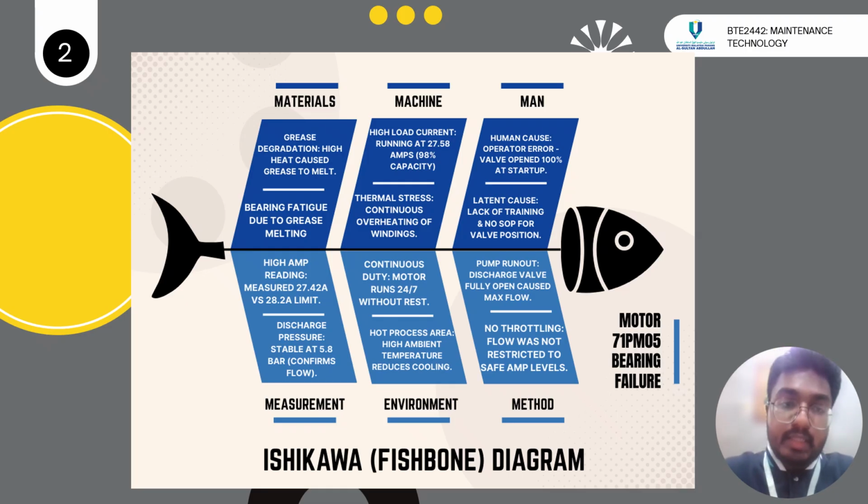So the third is the latent cause. Latent cause, this is the systematic issue. There was a lack of training regarding the pump curve and physics, and no SOP was in place to mark the correct valve position.